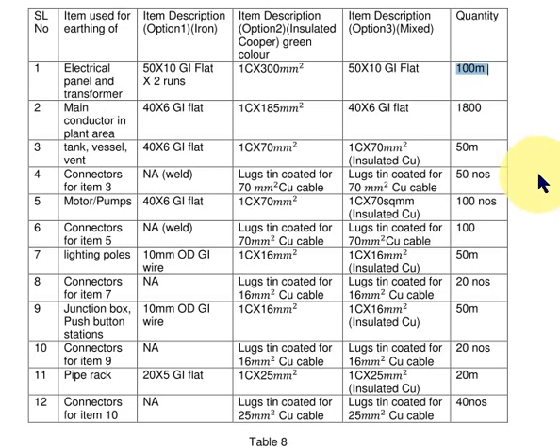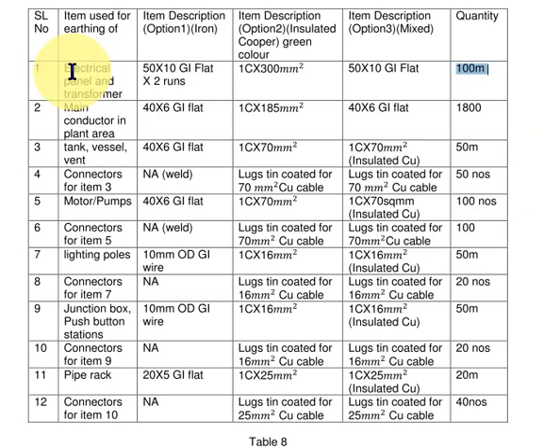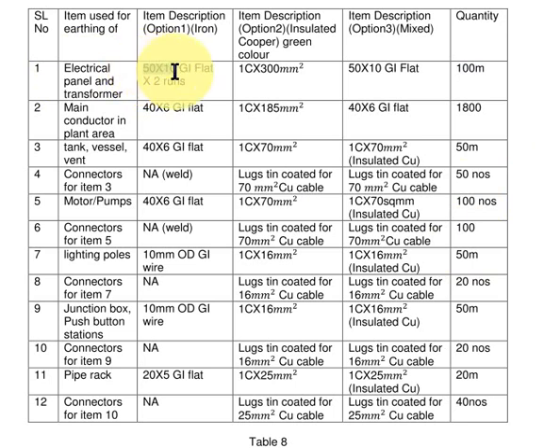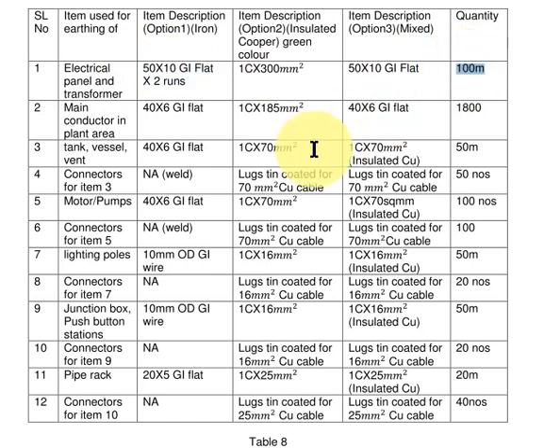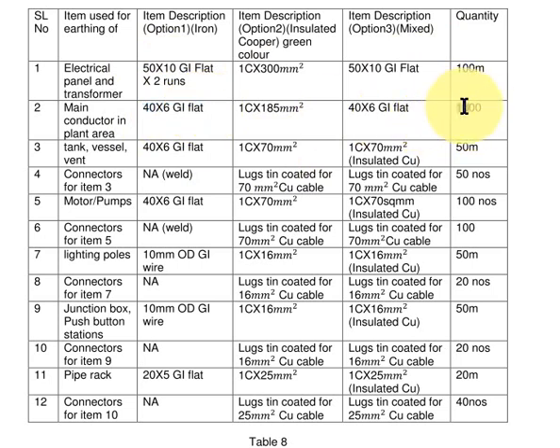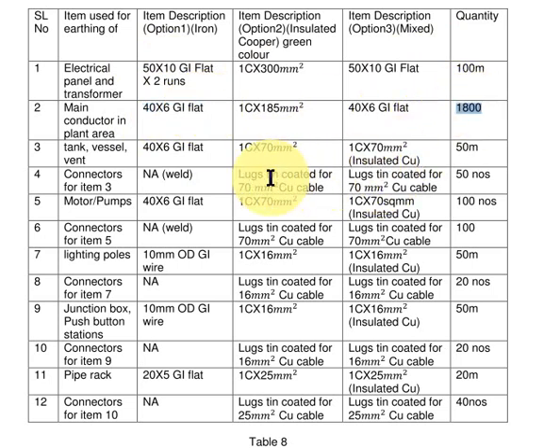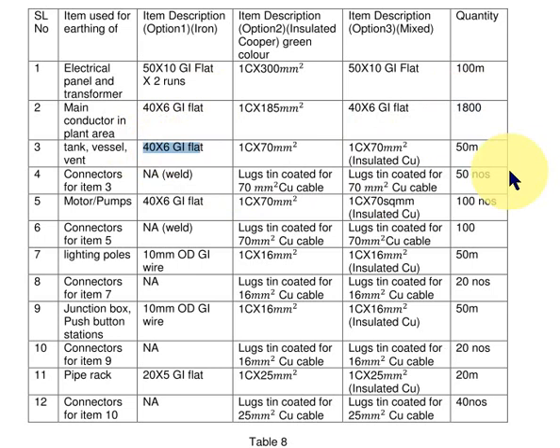In this example which we explained previously, the conductor used inside the electrical room or outdoor electrical area was 50 by 10 GI flat, 2 runs, so that was 100 meters. The conductor used inside the main plant area was 40 by 6 GI flat, so that was 1800 meters. The whole building of tanks, vessels, and vent used 40 by 6 GI flat, 50 meters.